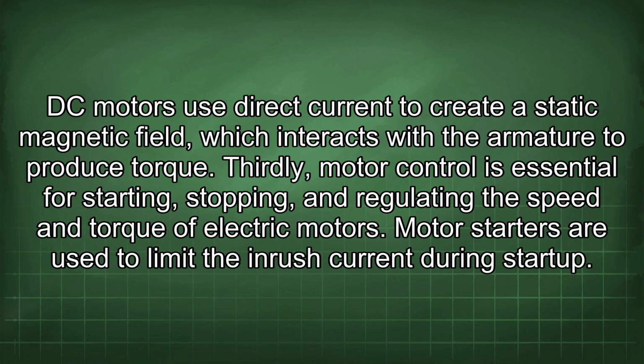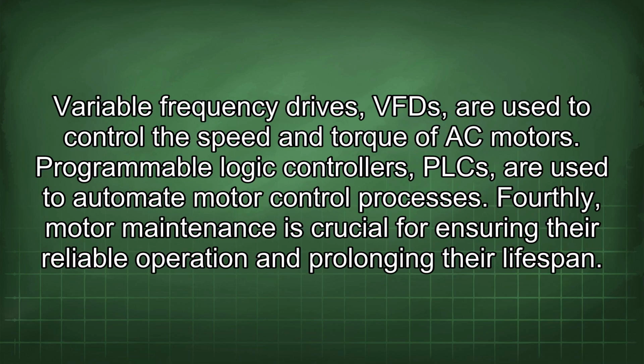Thirdly, motor control is essential for starting, stopping, and regulating the speed and torque of electric motors. Motor starters are used to limit the inrush current during startup. Variable frequency drives, VFDs, are used to control the speed and torque of AC motors. Programmable logic controllers, PLCs, are used to automate motor control processes. Fourthly, motor maintenance is crucial for ensuring their reliable operation and prolonging their lifespan.